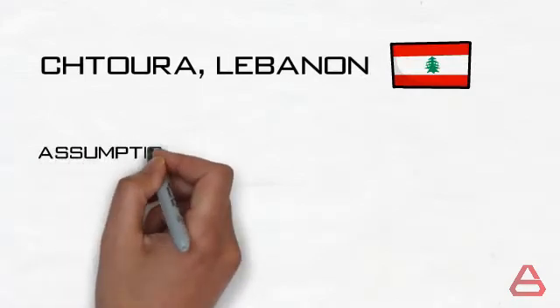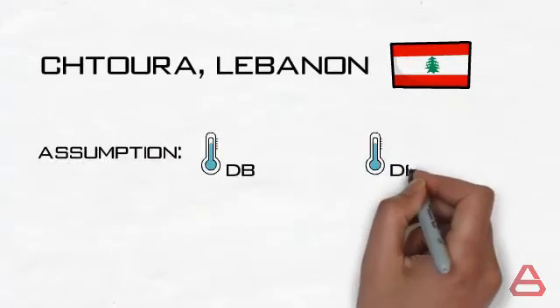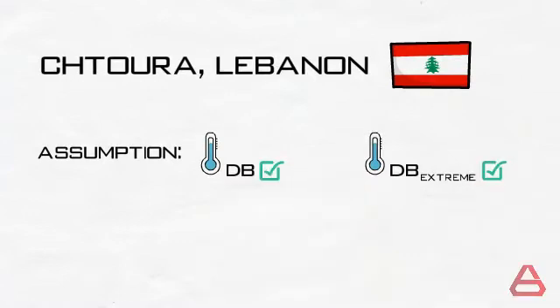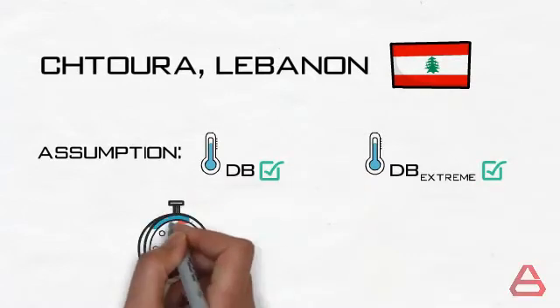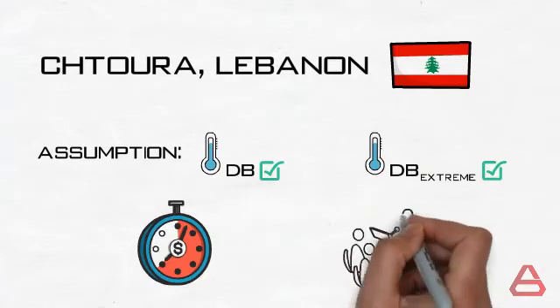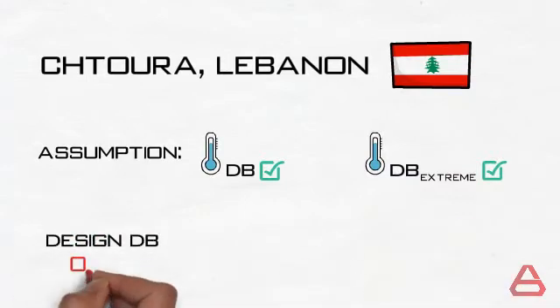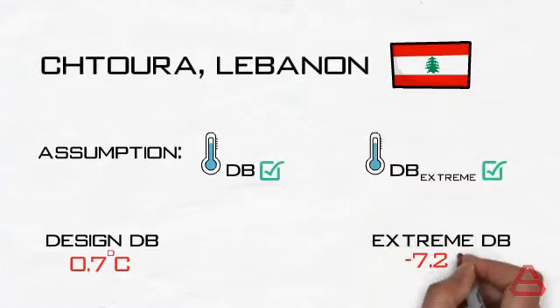Okay so back to Shtoura. We will consider for the time being that the design temperature and the extreme temperatures are given, just for the sake of delivering the idea. But keep in mind that shortly in this video I will show you how to select them using the ASHRAE tool. The design dry bulb temperature is 0.7 degrees Celsius while the extreme annual condition is minus 7.2 degrees Celsius for the lowest temperatures recorded at a frequency of 50 years.